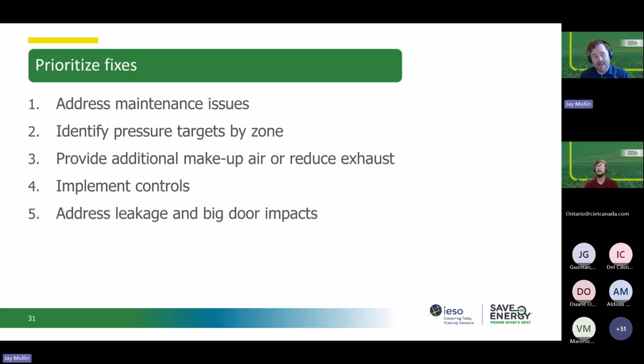So hopefully you've done all that. Once you've done all that and have a good sense of what's happening and have identified those solutions, you want to prioritize the fixes. And there is a good order to do this in. First, addressing those maintenance issues, things like outdoor air dampers. Are they open to the commanded position or what the control says it should be? Looking at the intake filters, screens, coils, make sure they're not choking flow. Relief dampers can actually relieve pressure, and BAS points are scaled correctly. Sensors are working, not installed in turbulent locations, giving poor readings, that sort of stuff. These are typically the lower cost issues to fix and can make a significant difference. So it's good to start with those.